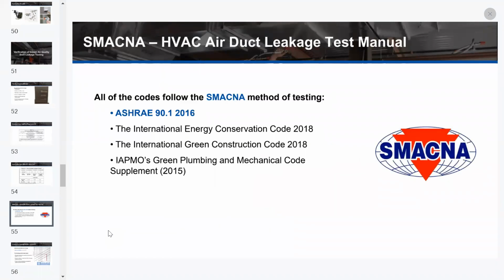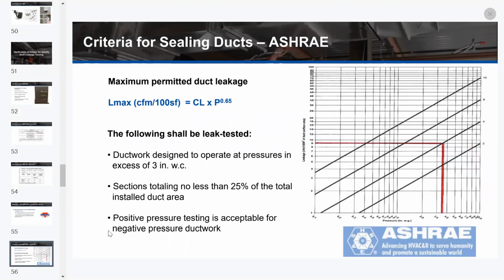Next is the SMACNA Air Leakage Test Manual. That is the guideline for how you will test, and it is tied in along with the International Energy Conservation Code, the International Green Construction Code, and IAPMO's Green Plumbing and Mechanical Code. And then ASHRAE 90.1. What's interesting about ASHRAE 90.1 is that it wasn't until ASHRAE 90.1-2010 that we required duct leakage testing on new construction. It is only a 25% representative sample of the system, but it's amazing that it wasn't until 2010 that we decided to really start testing and making sure the duct system was sealed.